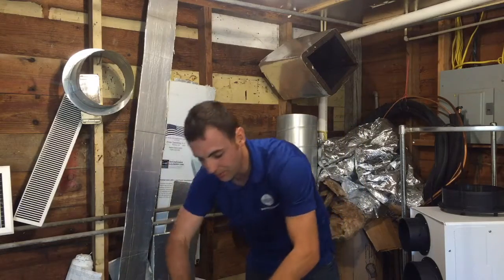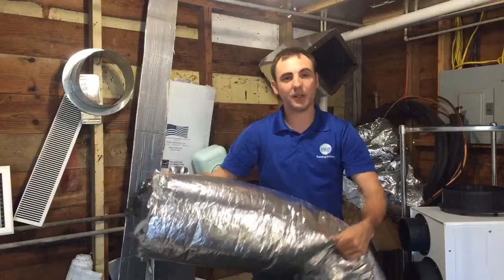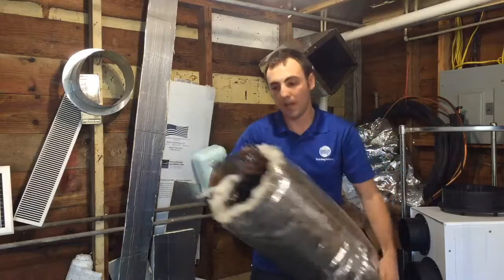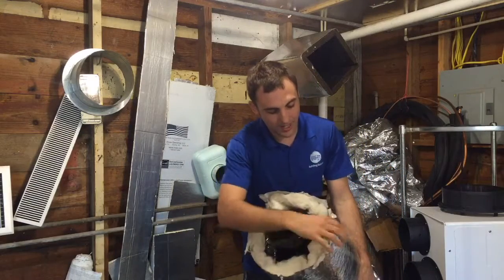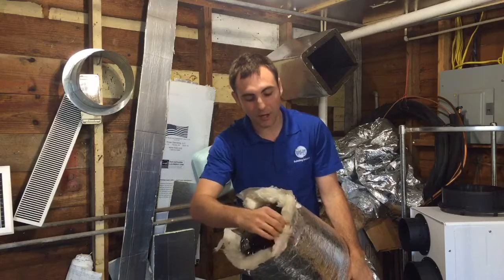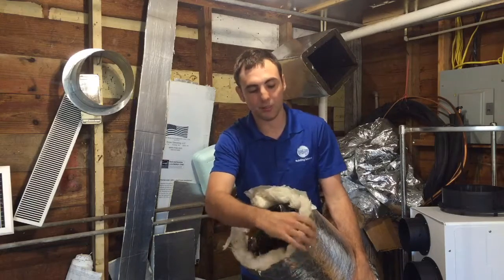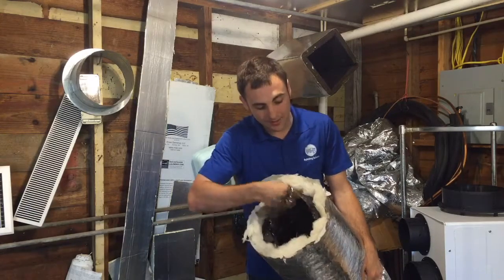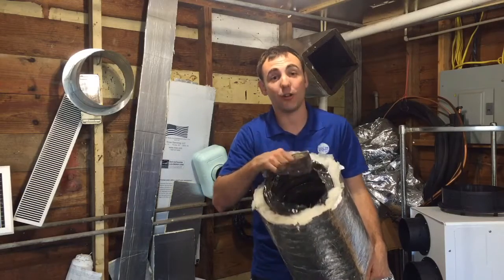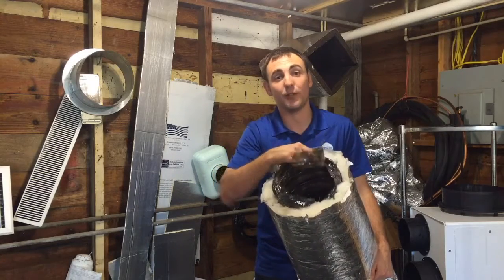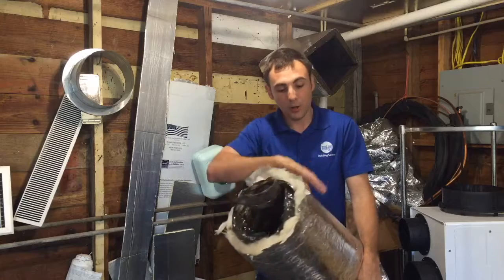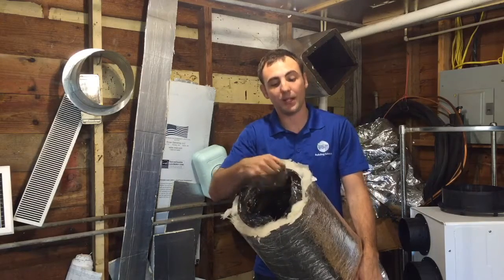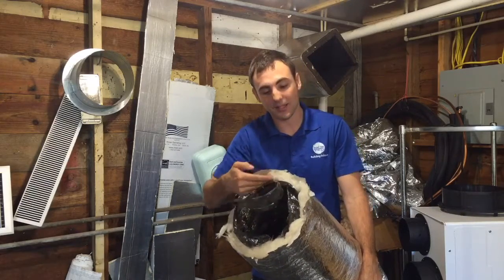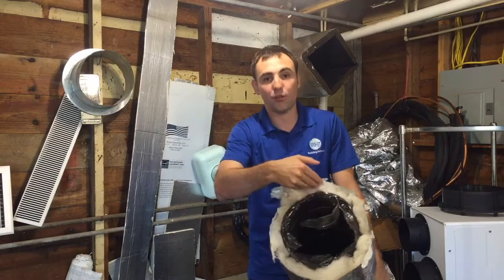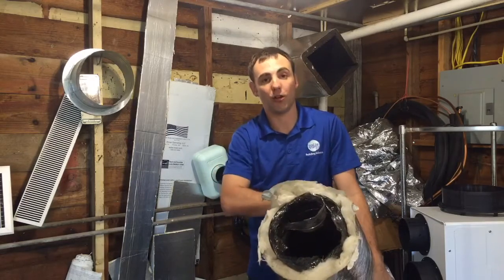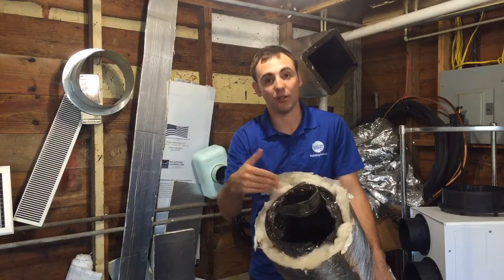Another example is this here. This is typically what flex duct looks like. The outside is sort of a little bit of a radiant barrier, and it holds the insulation in place and protects the insulation. The inside is the air liner. This is the important thing to get sealed from an air leakage perspective. Both layers need to be sealed, but this inside one is really important because if it's not sealed, then the air can just go straight through this insulation, and now you're ruining your R value with duct leakage inside your ducts.